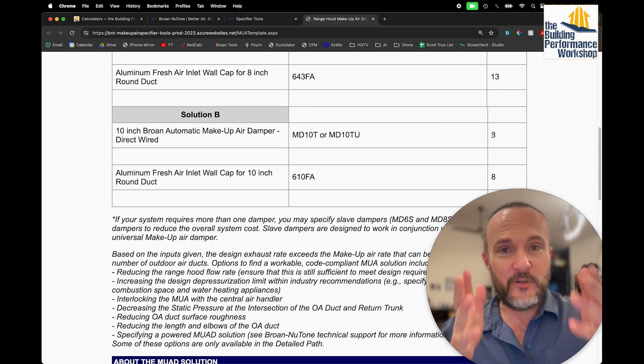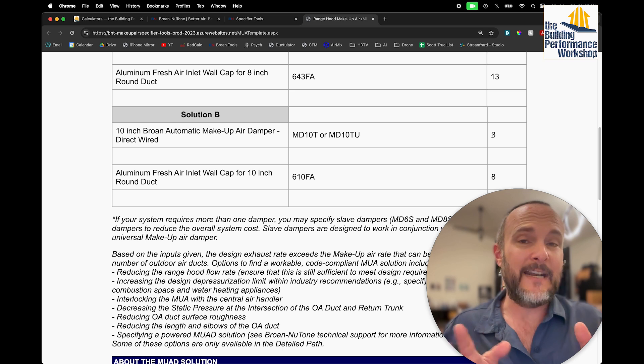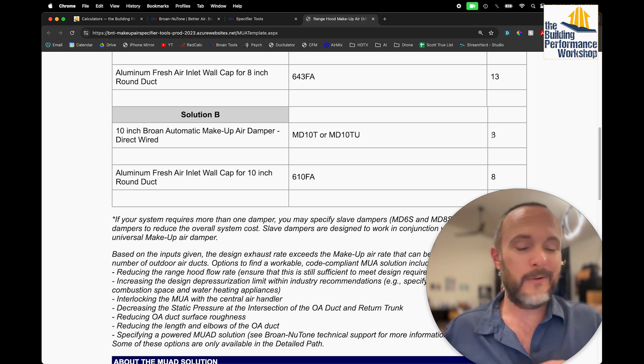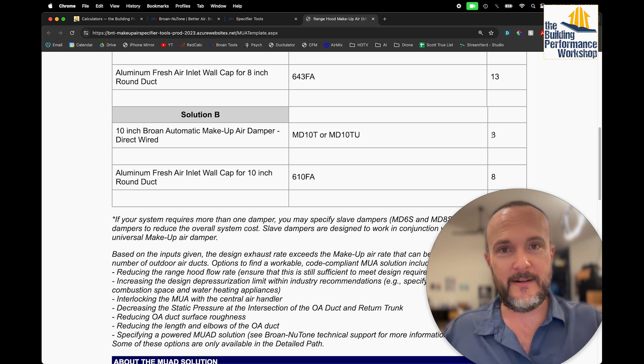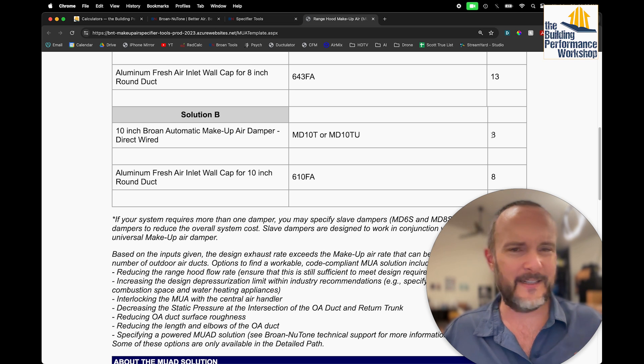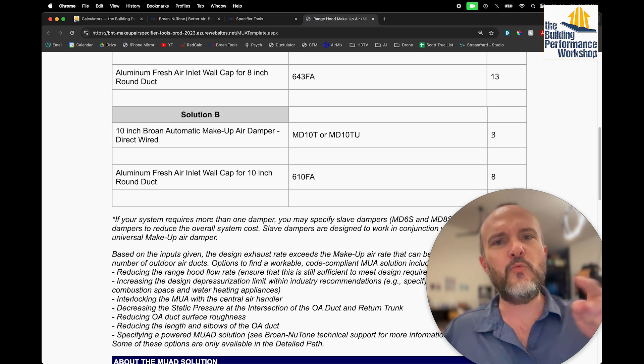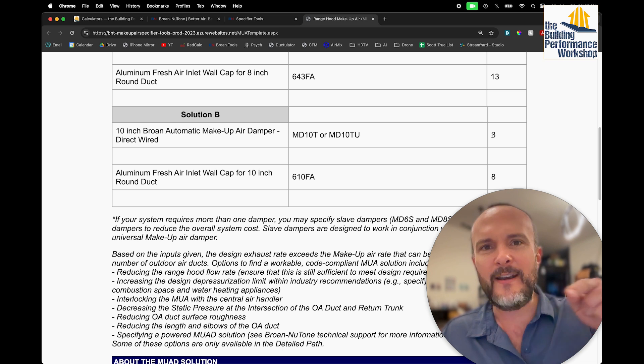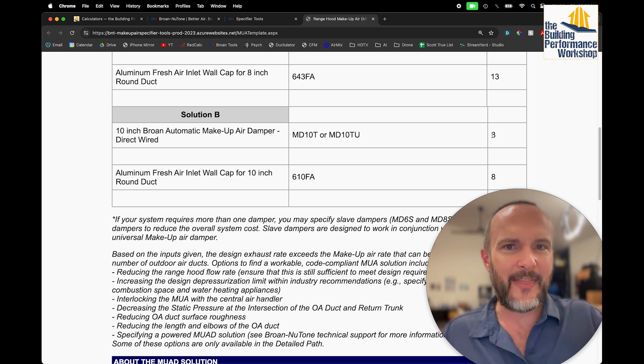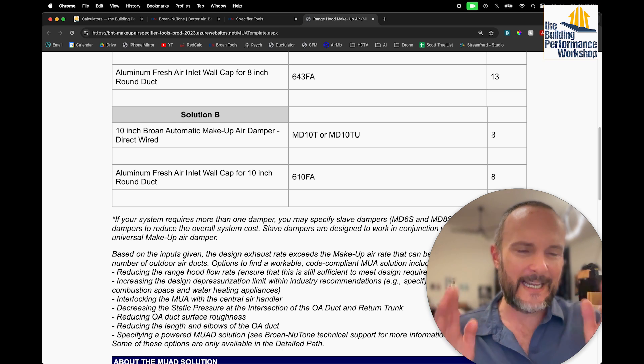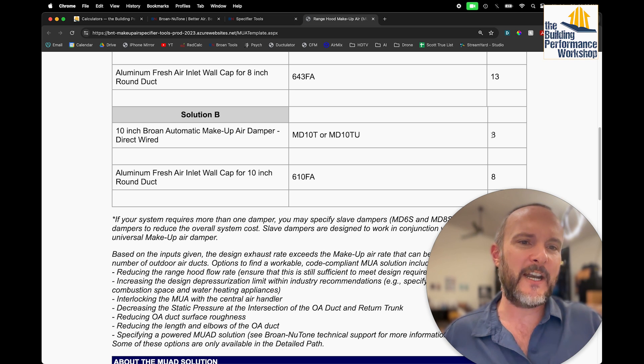This is why you generally, in a very airtight home, are not going to use passive makeup air. Because who wants to put 13 holes in their house? Nobody wants to do that. So this is where you go over to active makeup air. I have a video on calculating that as well, but I see this enough that I just wanted to make sure that people know 1 8-inch round is not going to do anything for makeup air.